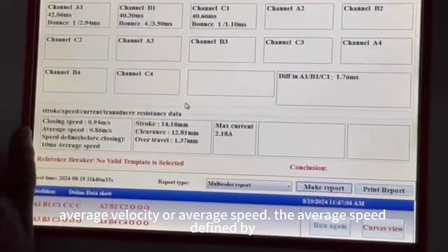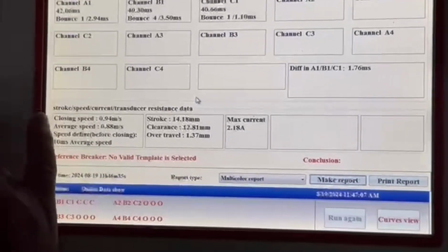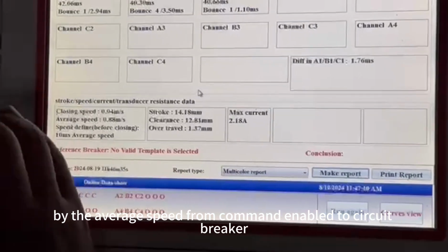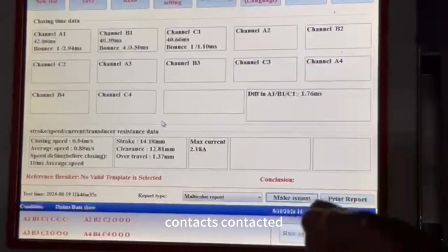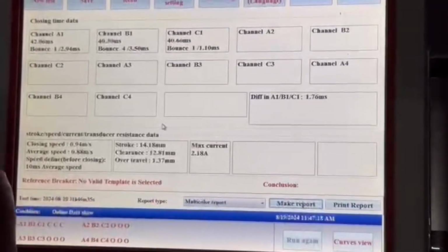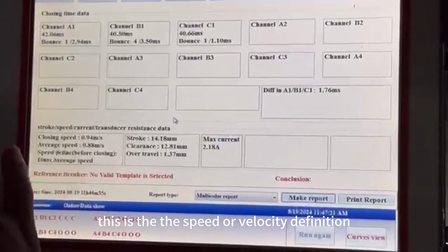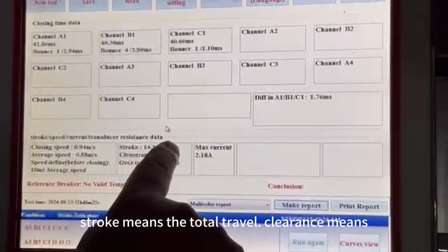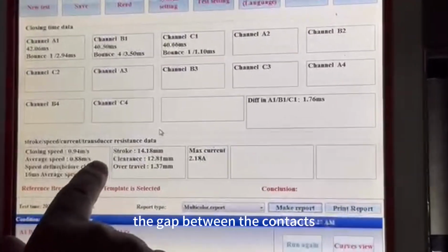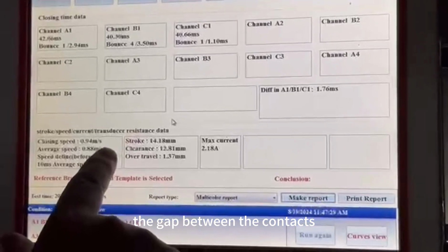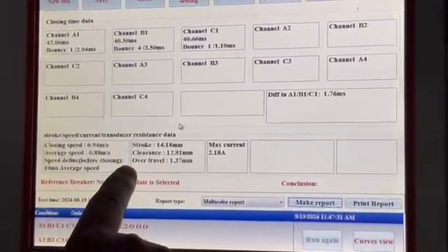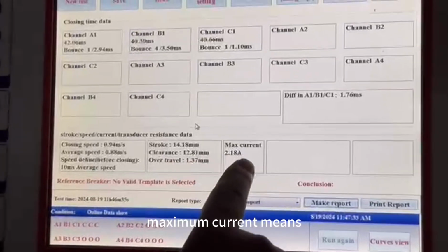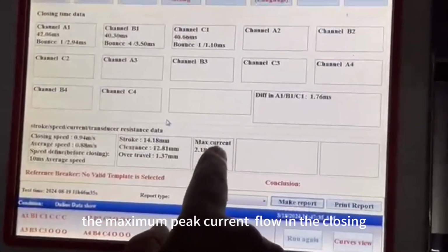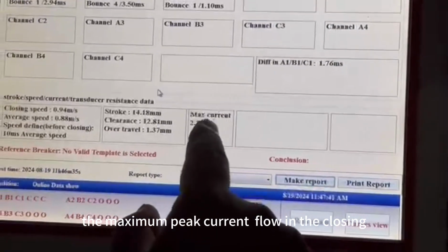The average speed is defined as the average speed from command enabled to circuit breaker contact. This is the speed definition or velocity definition. Stroke means the total travel. Contact travel means the gap between the contacts. The over travel. Maximum current means the maximum peak current flowing in the closing coil during the closing test.